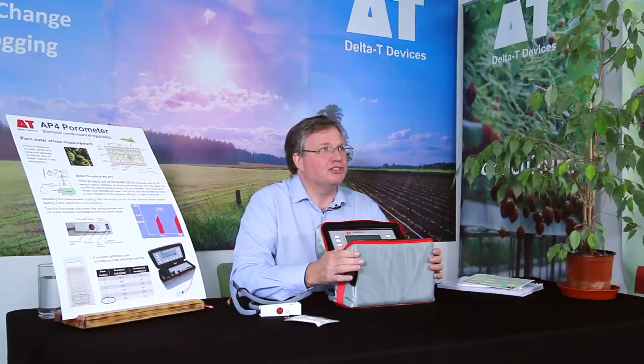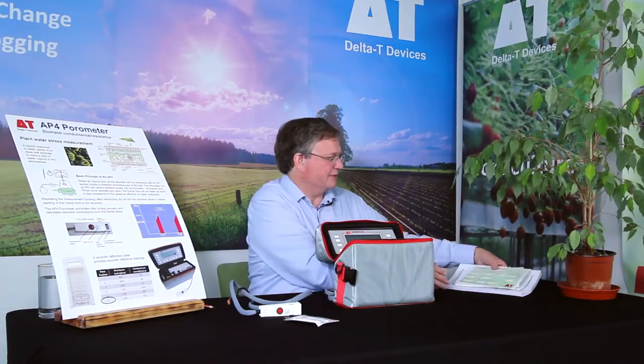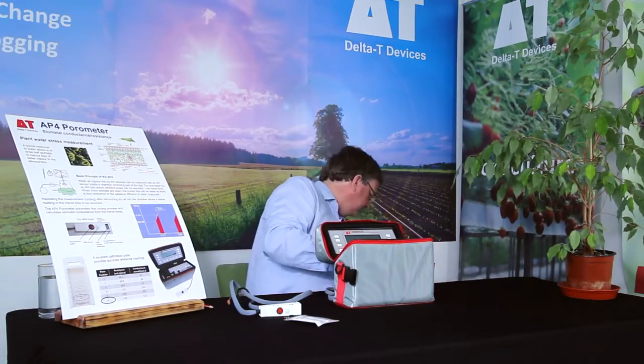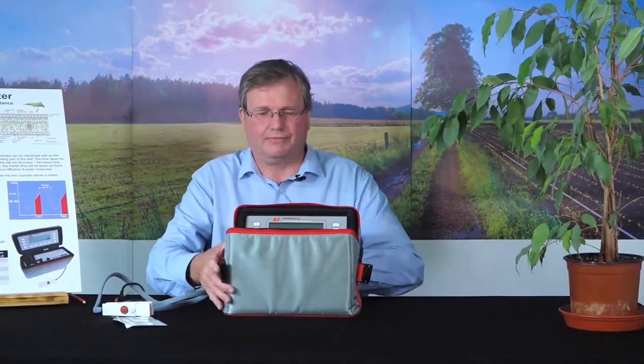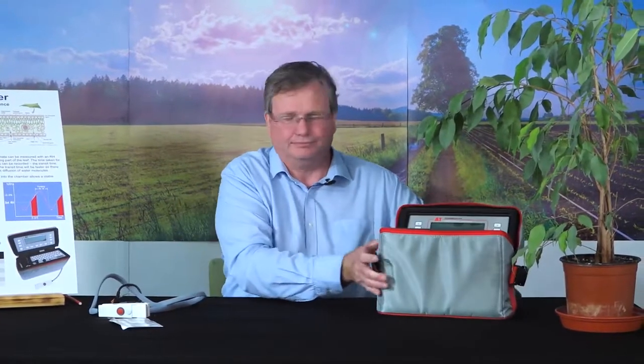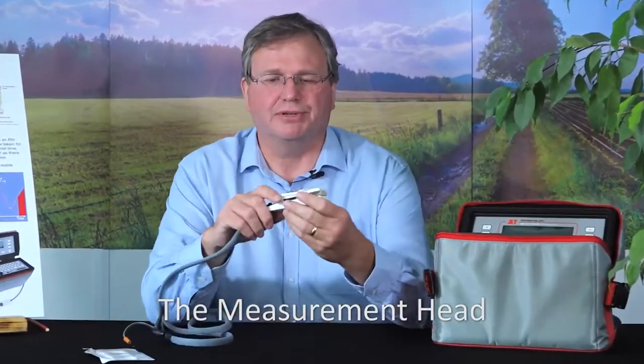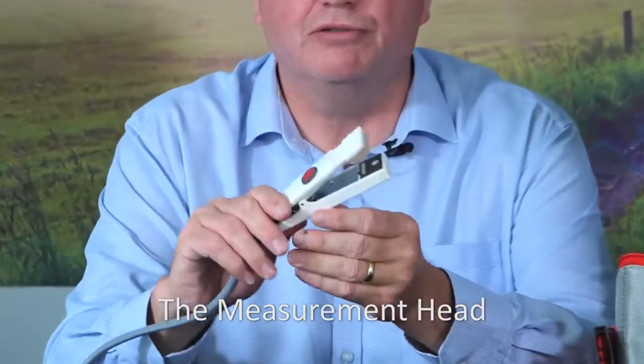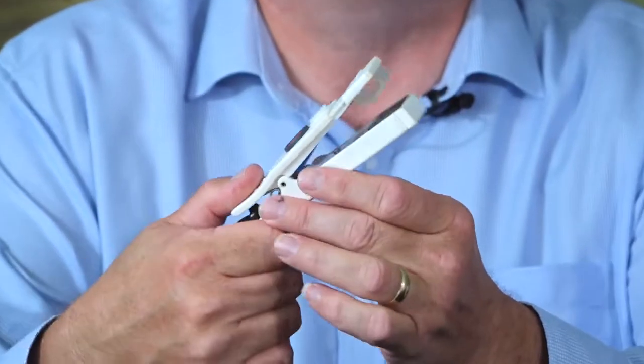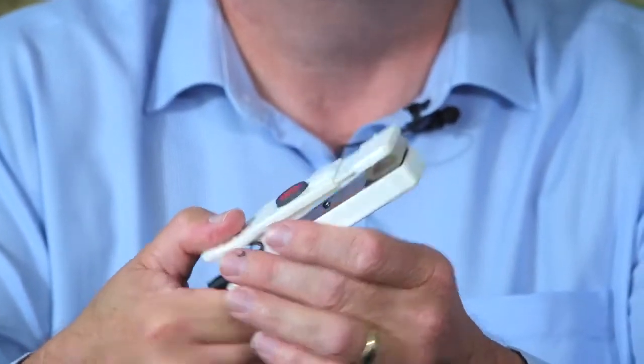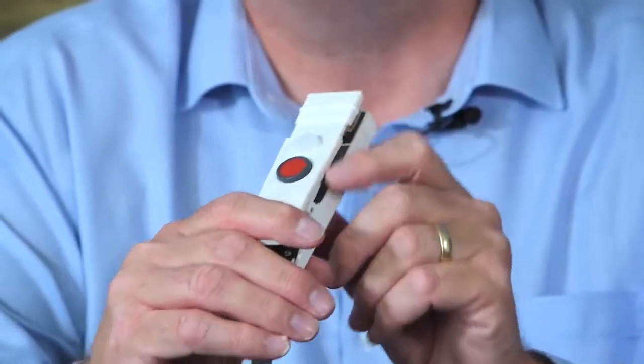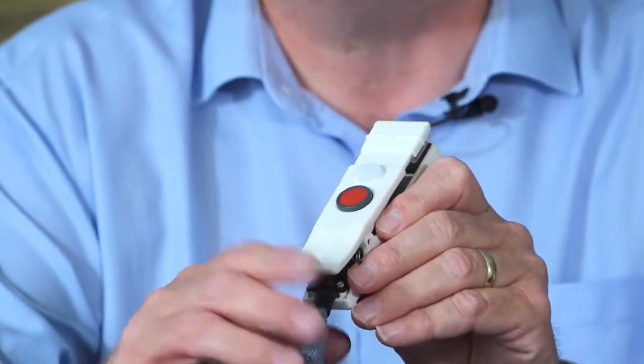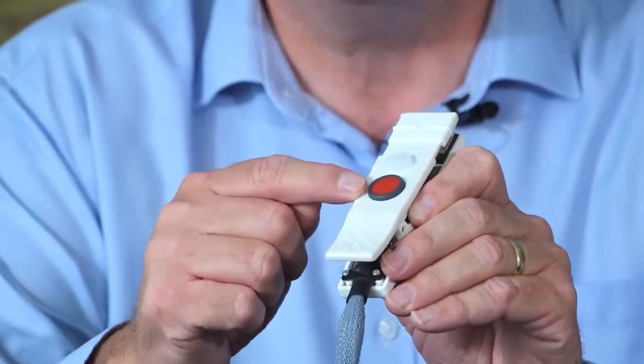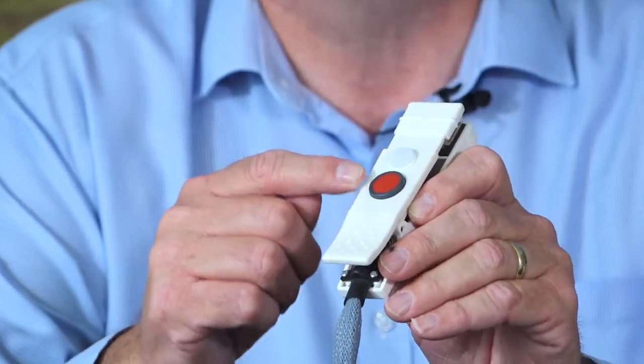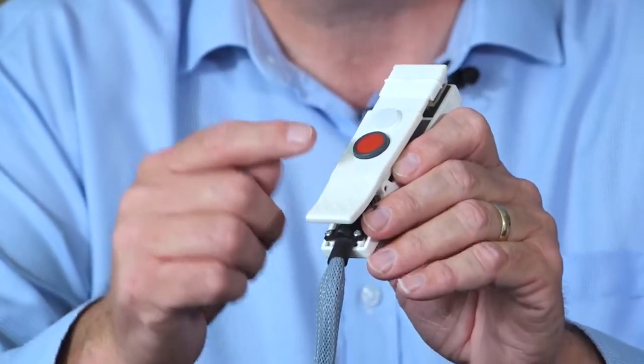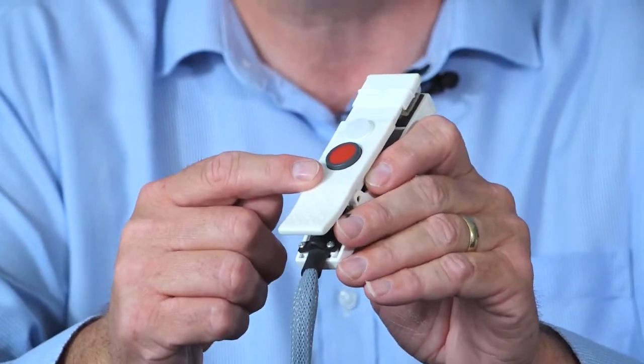So let's look at the measurement head. I'll just move these things out of the way. So the measurement head is a clip. It opens and closes, and that's what you put onto the leaf. On the top surface, you can see two very distinctive features and one a little bit more hidden. So the big red button, this is what you can press to accept a menu option and to start a reading, accept a measurement and store the measurement.